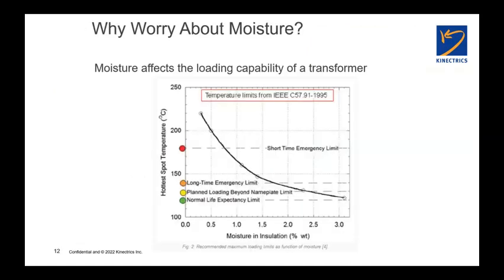This slide is speaking to the topic I mentioned about loadability. On the horizontal axis, we see the moisture content of the paper insulation in the transformer, and the hottest spot temperature in the winding, and increasing load. At some point, the moisture level becomes so high that we cannot tolerate a high temperature in the winding due to that bubble formation. So the higher the moisture, the more that effect is pronounced.